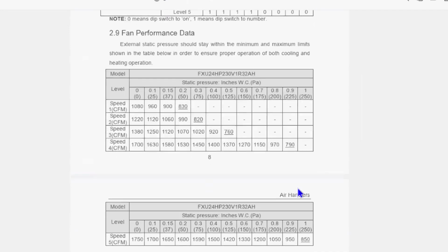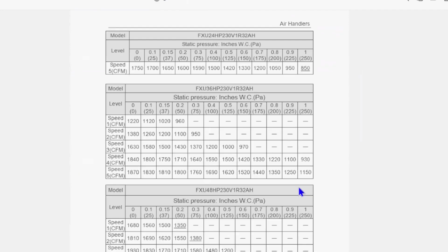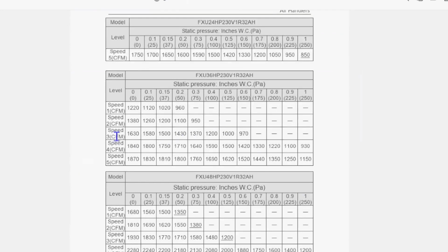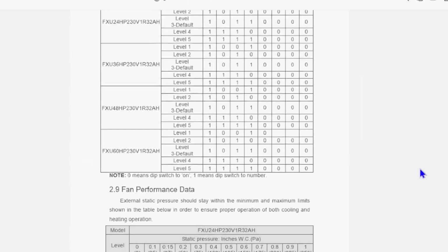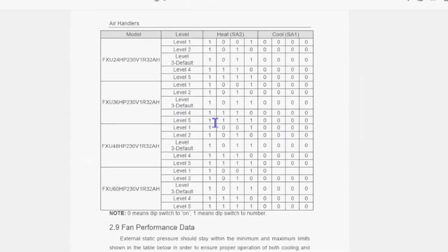We're going to go to the 3-ton fan performance data. We were at speed 3 at 0.5. That's only 1,000 CFM. So I'm moving 333 CFM per ton if I'm moving 1,000 CFM at a 0.5 total static, right? Yep. That's a little below what we like to see. It's a little low. I want to see at least 350. Go ahead and set them dip switches. You need 3-ton level 5, all off.